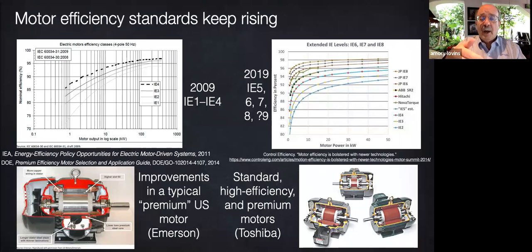Think about it inside out. 100% minus the efficiency is the losses, which make heat the biggest enemy of motors. So going from 92 to 96% efficiency cuts the losses, hence the heating, in half, from 8% to 4% of the input energy. And that can make the difference between active and passive cooling. And it makes a huge difference to reliability, which is often even more important to a factory's economics than efficiency is. Of course, the two go together.